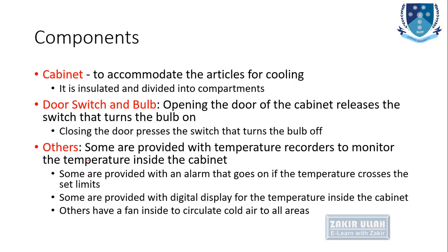And others which are present inside the cold incubators: temperature recorders to monitor temperature inside the cabinet. Some are provided with an alarm system that activates when the temperature is increased or decreased beyond the set values. Some incubators are provided with a digital display for the temperature inside the cabinet. Some incubators have a fan inside to circulate the cold air throughout the incubation chamber.